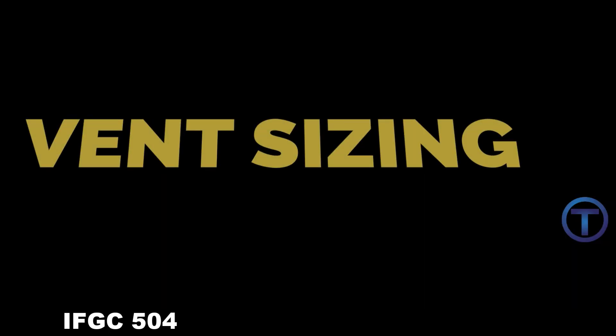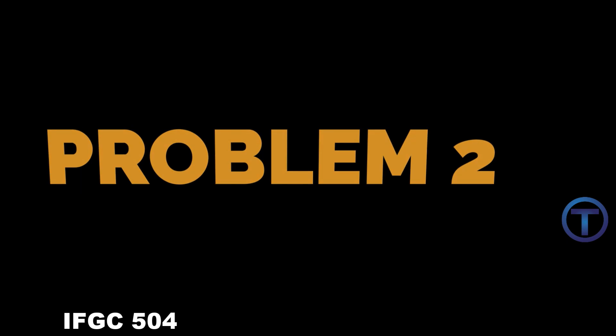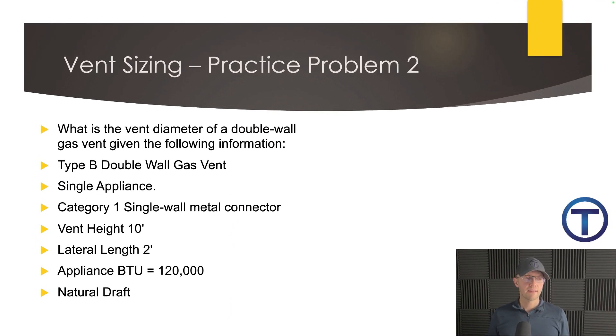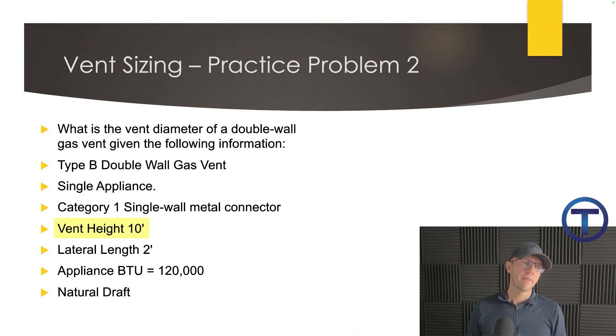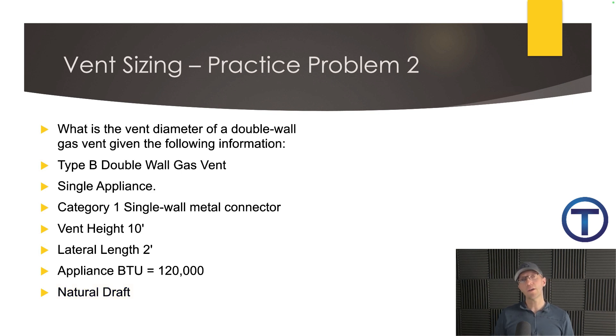Let's do one more. Practice problem two. Let's find the vent pipe for a type B double wall gas vent. We have a single appliance, Category 1, single wall metal connector — that's different than the last one, so we'll be on a different table. The vent height is 10 feet, lateral is 2 feet, appliance BTUs 120,000, and it's a natural draft. Pause the video here, try and find the table you should be using, figure out which size you'll be using, and we'll go from there.